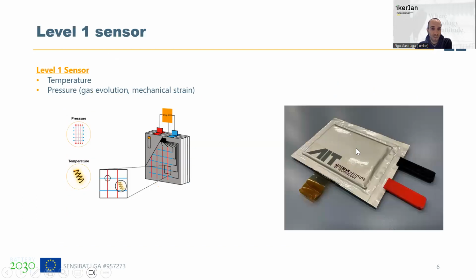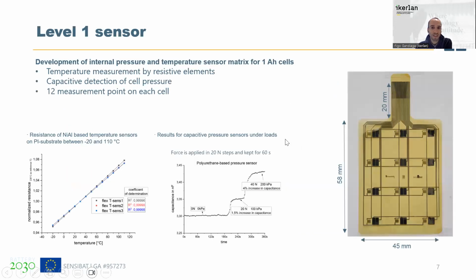So I am going to explain the level 1 sensor more in detail. This is the level 1 sensor for 1 ampere-hour cells. We measure the temperature by resistive elements, a nickel aluminum alloy, which, as you can see here, is quite linear from -20 degrees to 100 degrees Celsius.